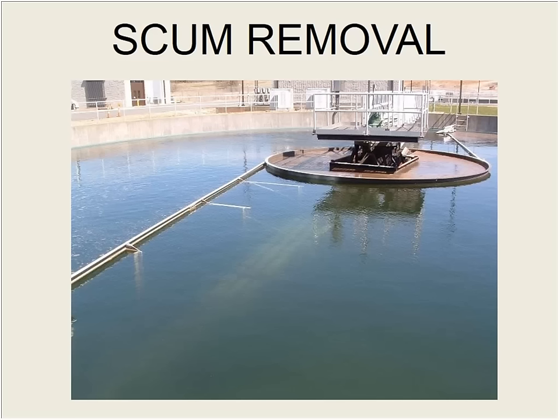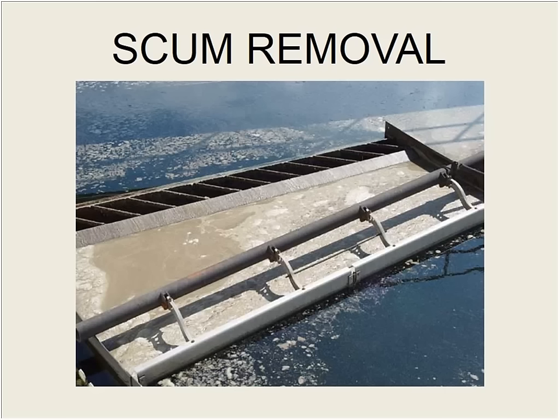For any floatable material, this arm is going to pick it up and push it around, and it's going to come up to this wiper here that runs it up this little ramp, and it'll drop down into this opening here to remove the floatables from the water. Sludge goes to the bottom, gets plowed into the sump. It's pumped away.